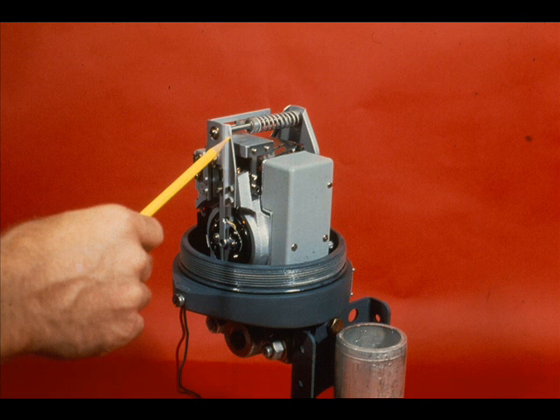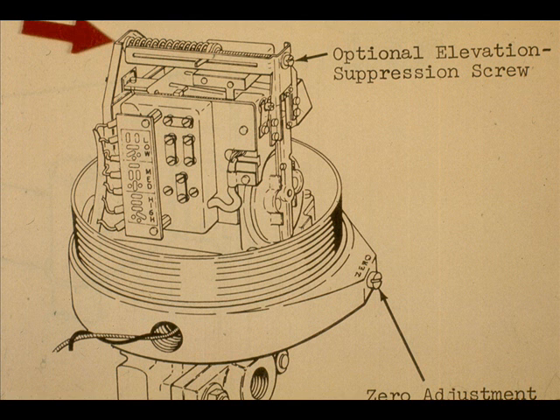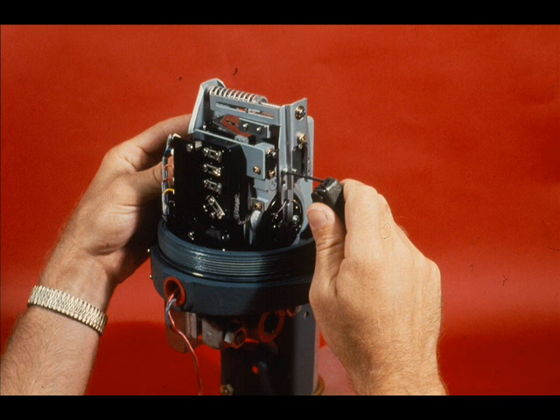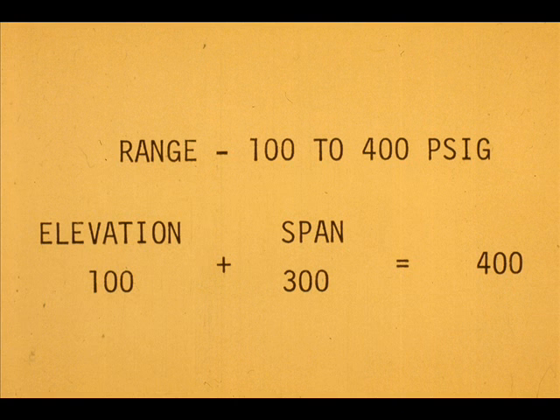For any range that begins below or above zero, the Foxboro transmitter requires the installation of an optional elevation suppression unit, also called a bias unit. It is very easy to install by referring to pictures in the instruction manual and installing the screws and nuts furnished with the unit. Foxboro calls pressure ranges beginning above zero elevated ranges, and those beginning below zero suppressed ranges. The elevation plus the span for a given capsule must not exceed the upper range limit.